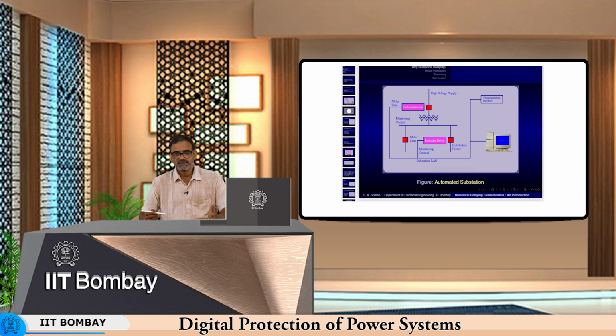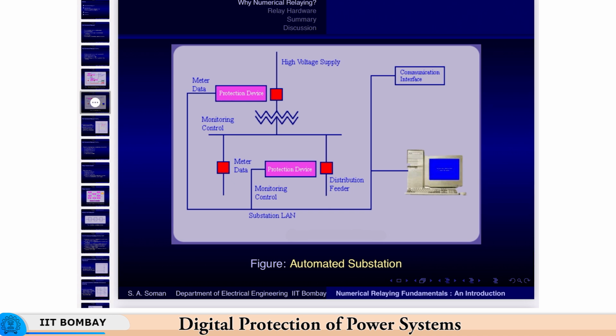In a small substation, the wiring doesn't matter much, but in a very large 400 kV substation handling say 1000 megawatts of power, the cabling itself runs into kilometers and kilometers. So even that can be avoided and simplified. It is a big plus for operations engineers, maintenance engineers, protection engineers, and control engineers. So this is one of the ways we can leverage the power of numerical relays.